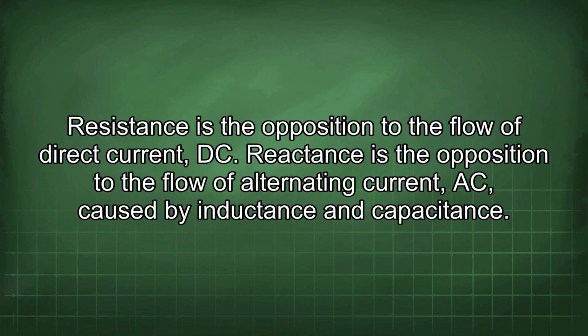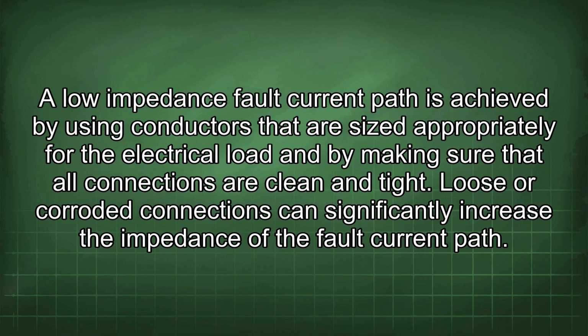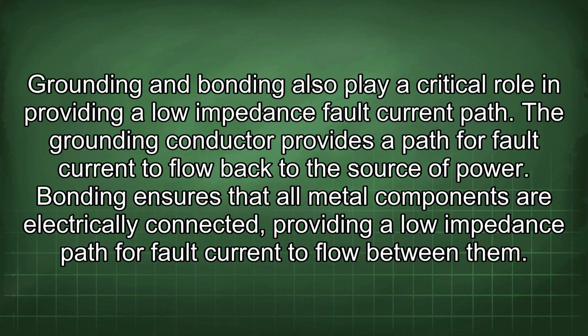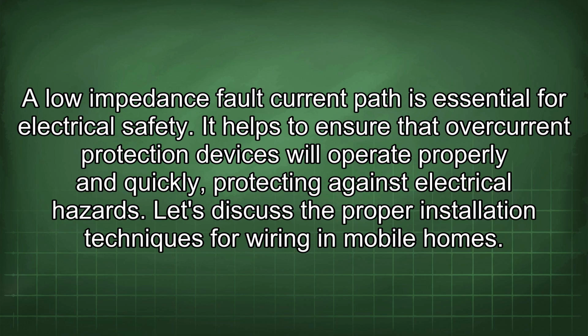Resistance is the opposition to the flow of direct current, DC. Reactance is the opposition to the flow of alternating current, AC, caused by inductance and capacitance. A low impedance fault current path is achieved by using conductors that are sized appropriately for the electrical load and by making sure that all connections are clean and tight. Loose or corroded connections can significantly increase the impedance of the fault current path. Grounding and bonding also play a critical role in providing a low impedance fault current path. The grounding conductor provides a path for fault current to flow back to the source of power. Bonding ensures that all metal components are electrically connected, providing a low impedance path for fault current to flow between them. A low impedance fault current path is essential for electrical safety. It helps to ensure that overcurrent protection devices will operate properly and quickly, protecting against electrical hazards.